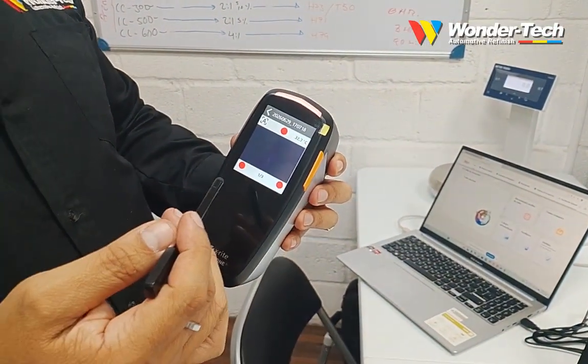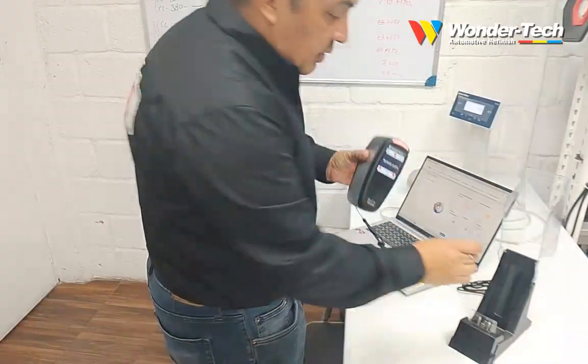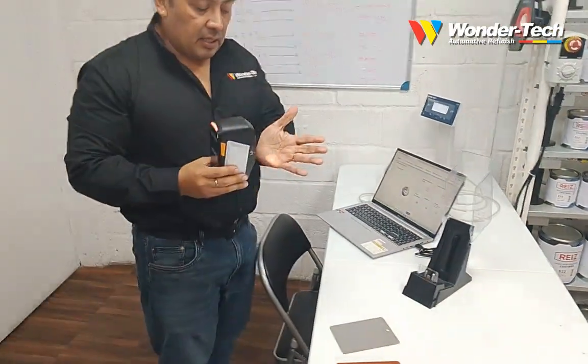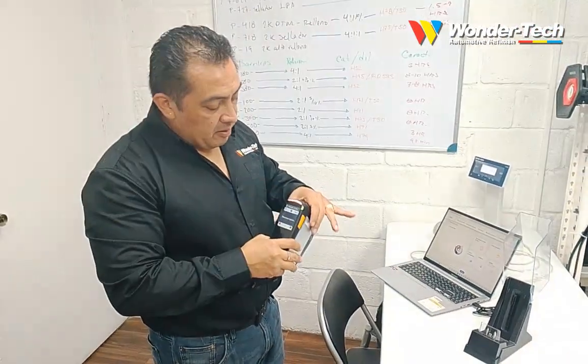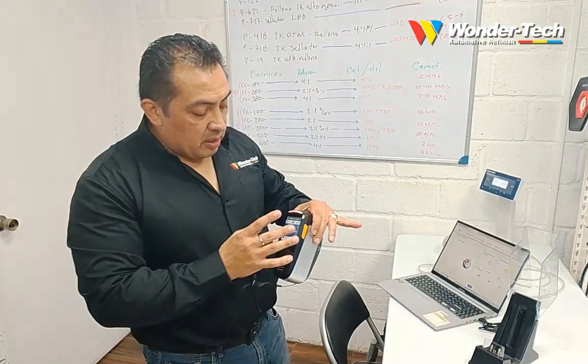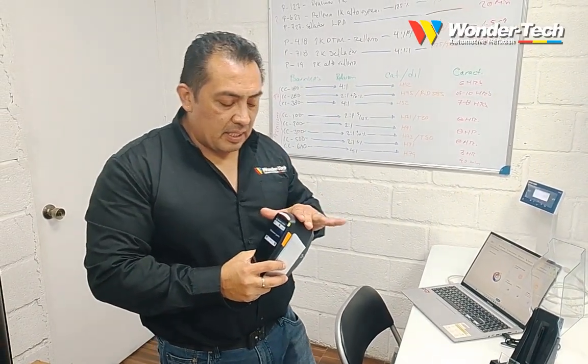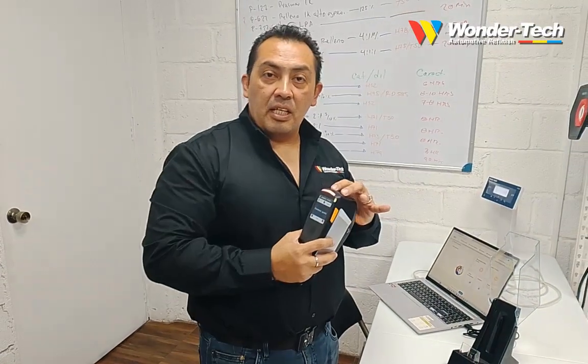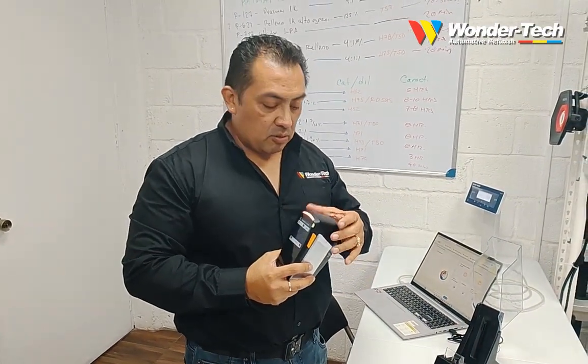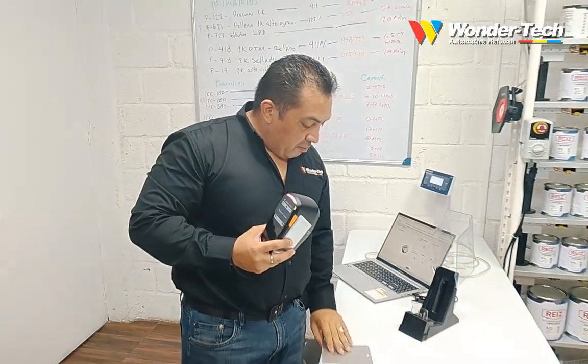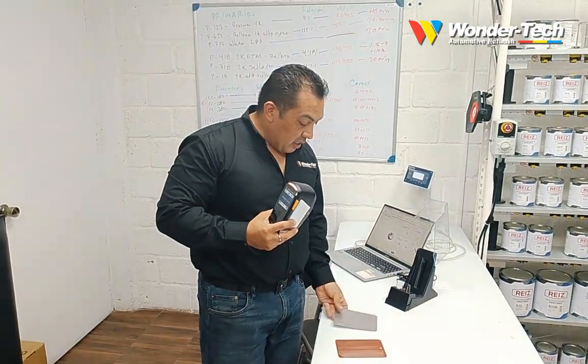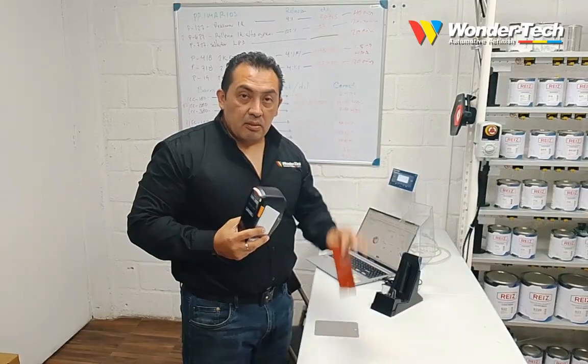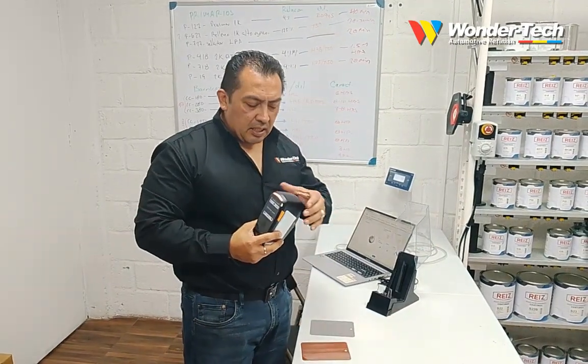As you can see, the device features a built-in high-definition camera. The spectrophotometer can operate in either automatic mode or manual mode. For convenience, I have mine set to automatic mode. I also want to point out that the instrument is capable of measuring the gloss level of the sample in addition to its color. To demonstrate this feature, we'll measure 4 different samples: 1 matte finish, 1 gloss finish, 2 additional gloss finishes.